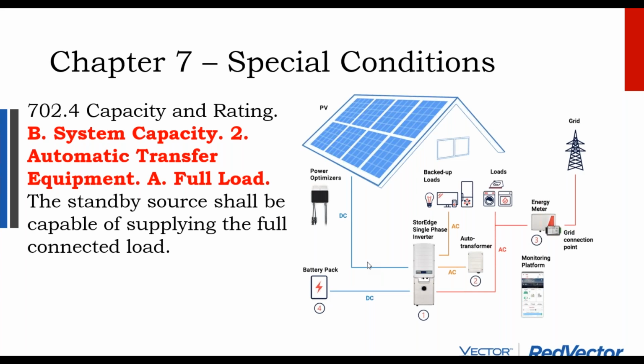But in terms of that backup power capability, the code says your backup power supplies still have to adequately power what they're backing up. You can't just say, oh, well, I'm going to feed 8 kilowatts of power into my home service panel and hopefully it'll power everything, but it might not. You're not allowed to guess like that.